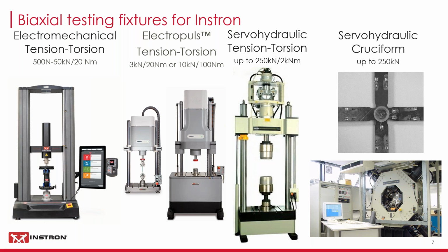And we've supplied machines like that with RF heating for metallic specimens, and things like confocal microscopes, which look at the center of the specimen. And again, because the center of the specimen is stationary, you can actually do things like imaging and look in detail at crack growth, which is a very powerful feature of a machine like that.